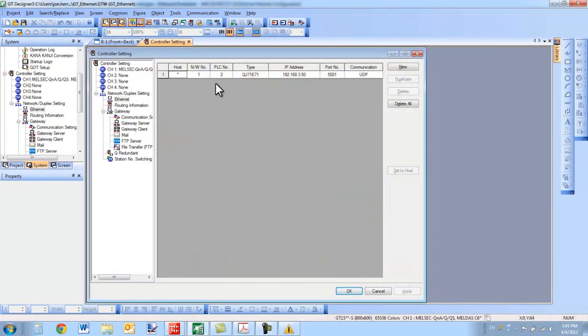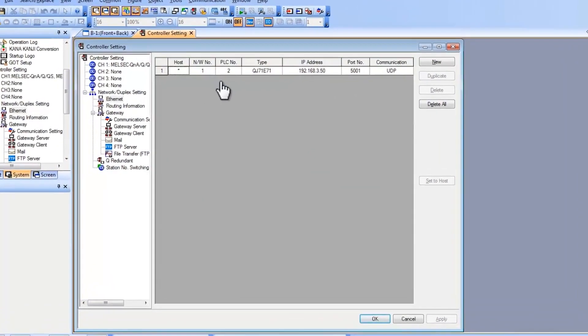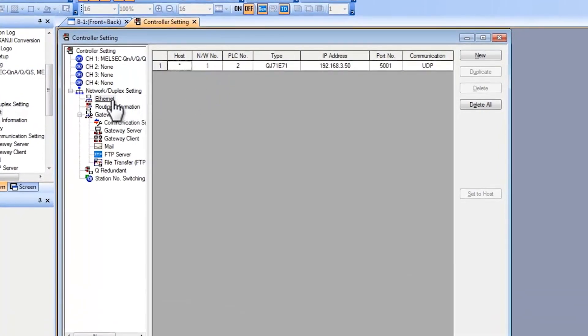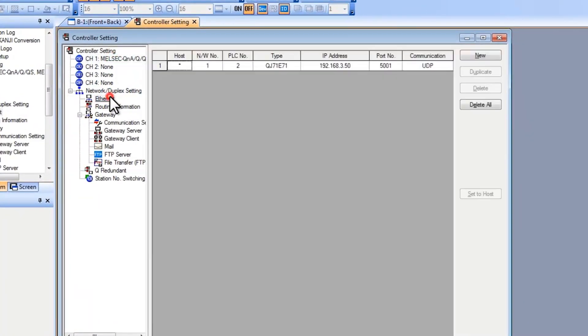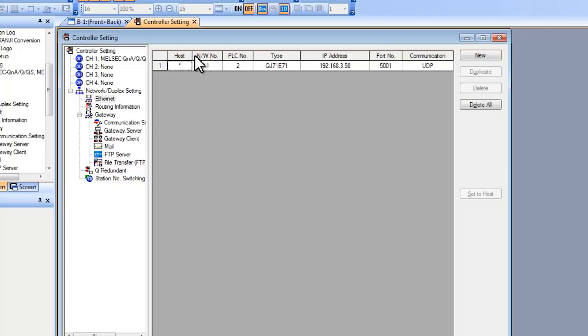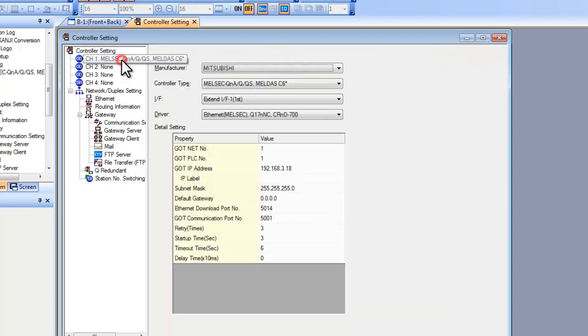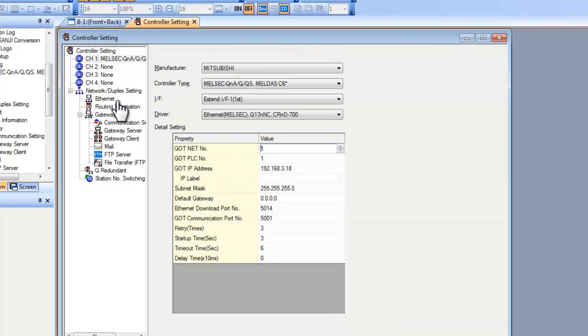These are the two most important settings on the GOT. You have your Ethernet setup and your channel setup. For the Ethernet setup you need to make sure that your network number and your PLC number are configured correctly. For the network number set this to 1. This needs to match in the channel settings the GOT network number. Make sure these are the same.